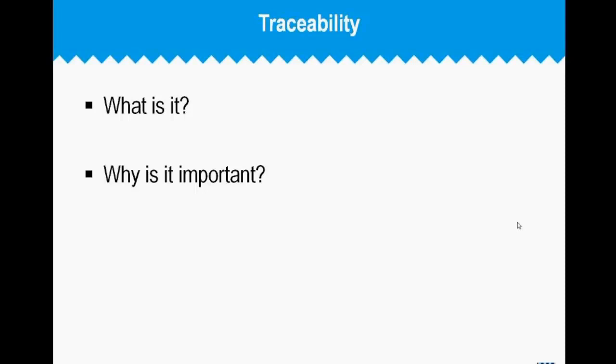Some horror stories that I've seen are examples where you go into a supplier or you're working with a client, and you start looking at their documentation around traceability, and you start discovering that all the documentation was essentially generated in the last month of this one-year project. And you start digging into the why, and it's because they really didn't create and baseline those artifacts through their particular process as they were going through that process. Instead, they try to bolt on traceability at the end of the process and show that traceability through that.